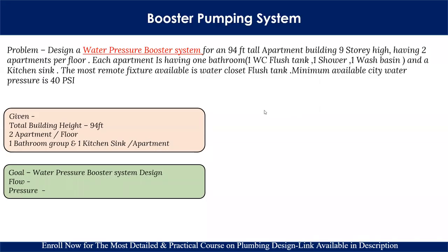Let's understand the direct pressurized system with the help of an example. In this problem, we have to design a water pressure booster system for a 94-feet-tall apartment building. The building type is an apartment, nine stories high, having two apartments per floor. Each apartment serves one bathroom with a flush tank WC, one shower, one wash basin, and a kitchen sink. The most remote fixture is the water closet — the farthest fixture from the booster set. The minimum available city water pressure is 40 psi.